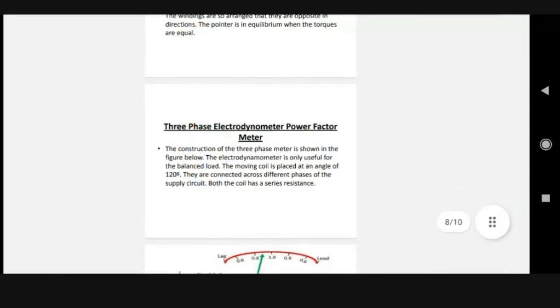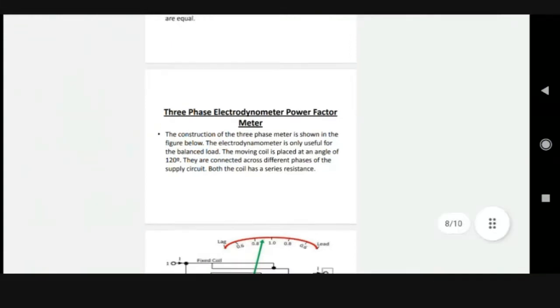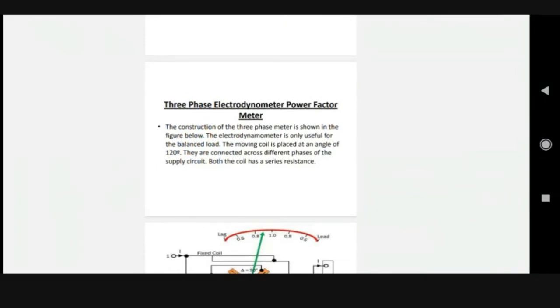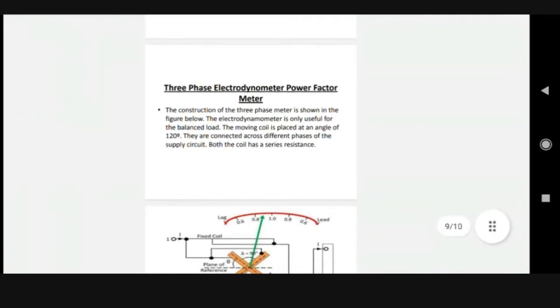Now we are going to study the construction of the three-phase electrodynamometer power factor meter. This power factor meter has the same construction as the single-phase power factor meter. This instrument is not affected by variation in frequency. The main difference in construction between the single-phase and three-phase power factor meter is that the moving coils are placed at an angle of 120 degrees. They are connected across different phases of the supply circuit.